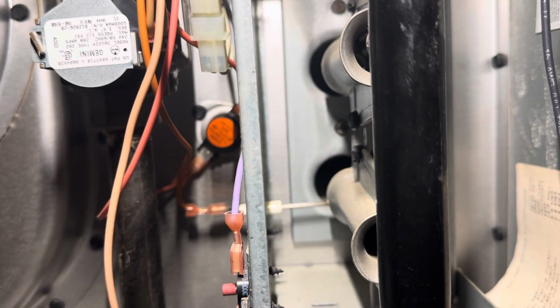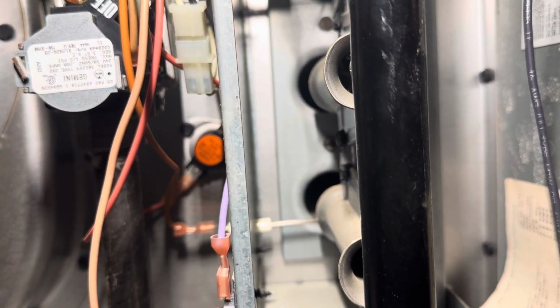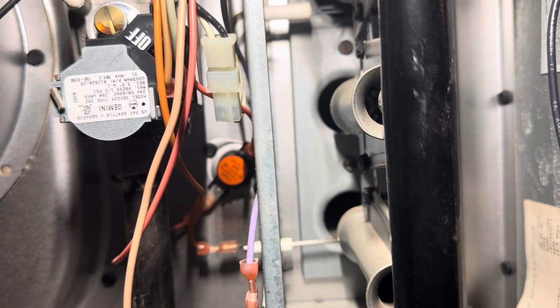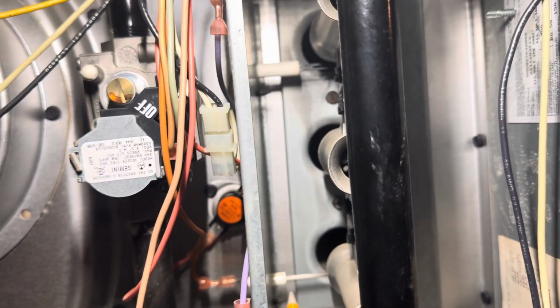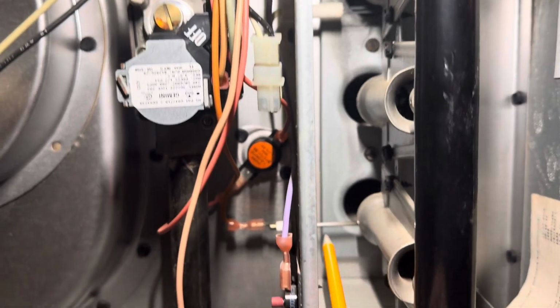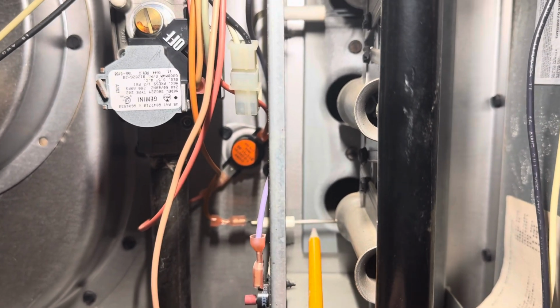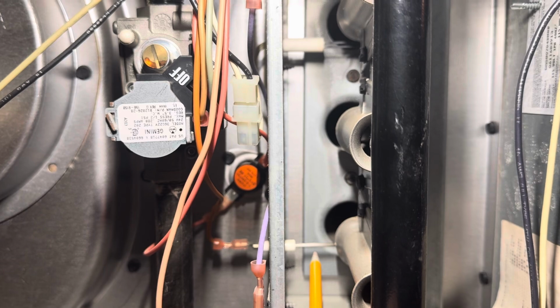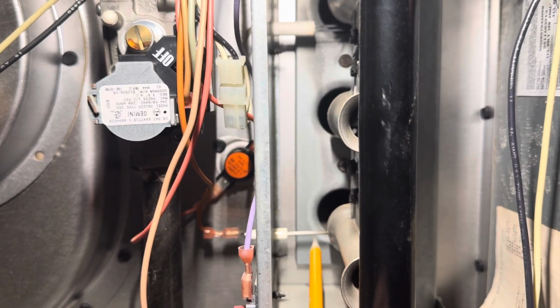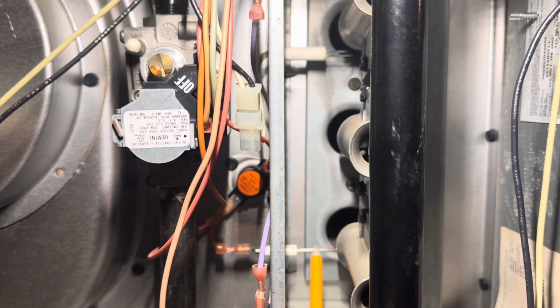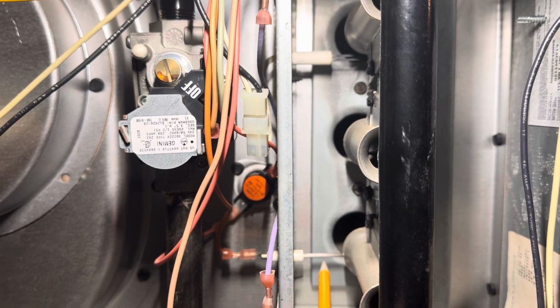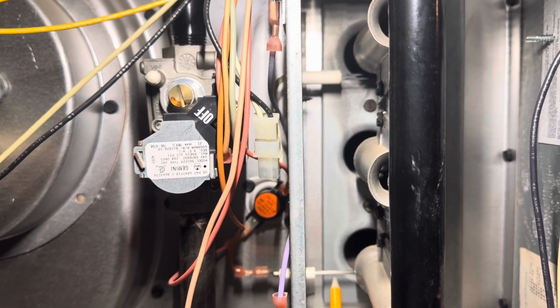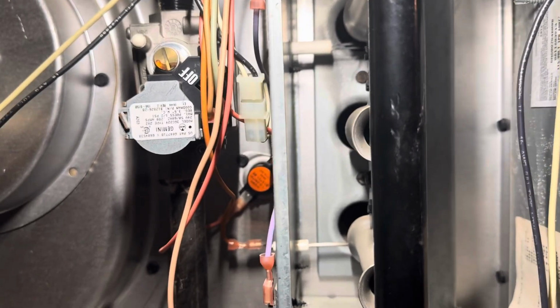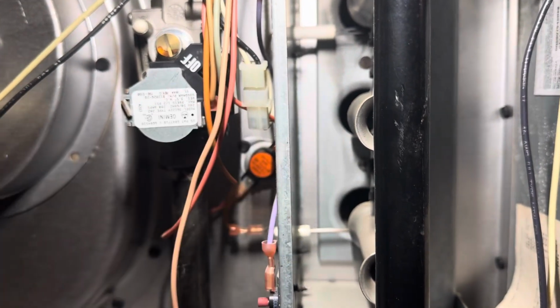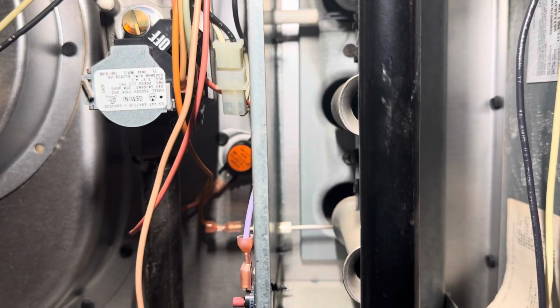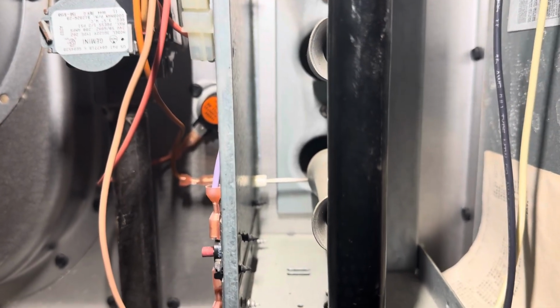So if there's not flame, the unit will shut down. I'll tell you, this is a common point of failure in that the flame rod gets dirty with carbon, and you need to every season remove this and clean it with a Scotch-Brite pad like this one. And I will put a link in the description of how to do that.